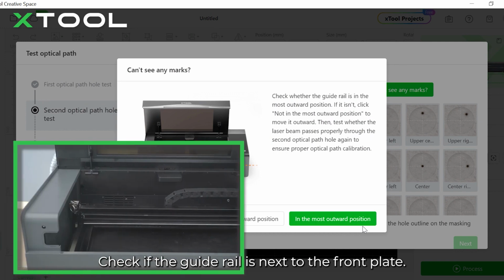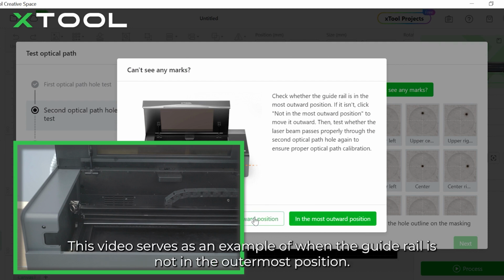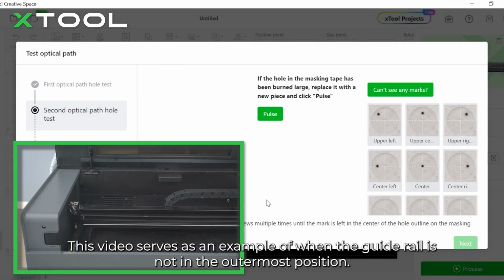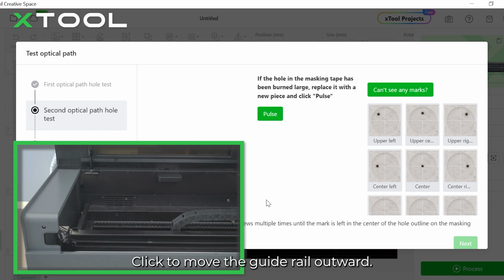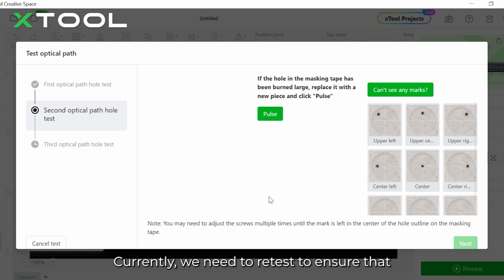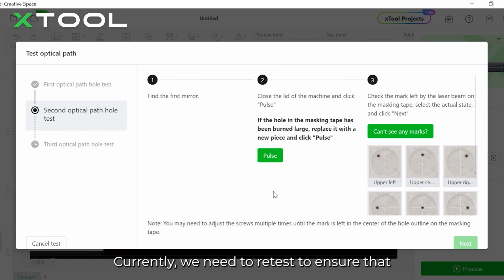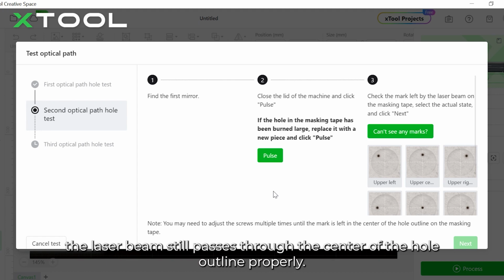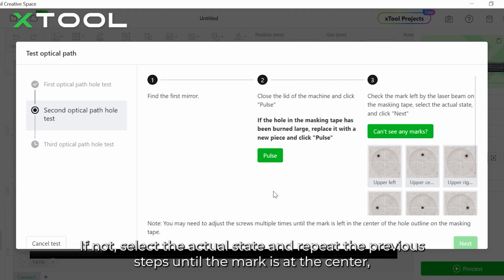Check if the guide rail is next to the front plate. If not, click Not in the most outward position. This video serves as an example of when the guide rail is not in the outermost position. Click to move the guide rail outward. Currently, we need to retest to ensure that the laser beam still passes through the center of the hole outline properly. If not, select the actual state and repeat the previous steps until the mark is at the center.